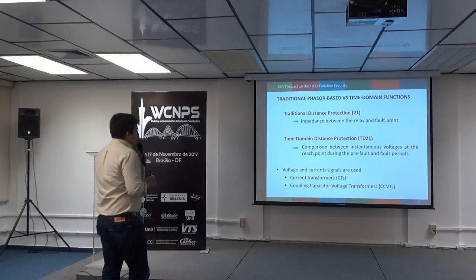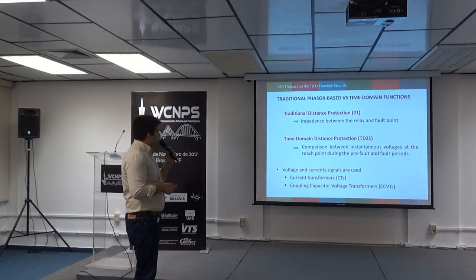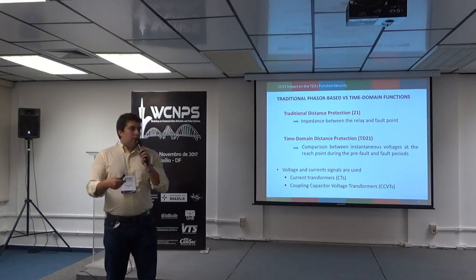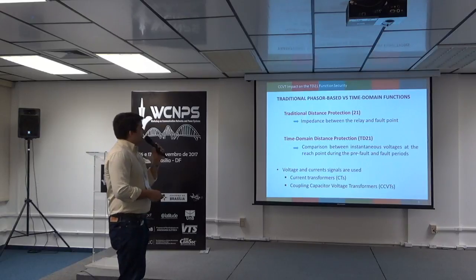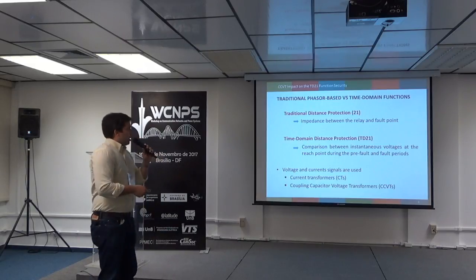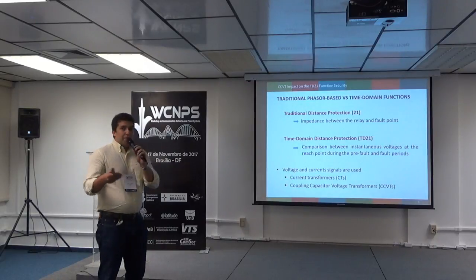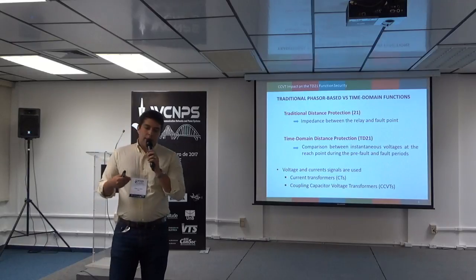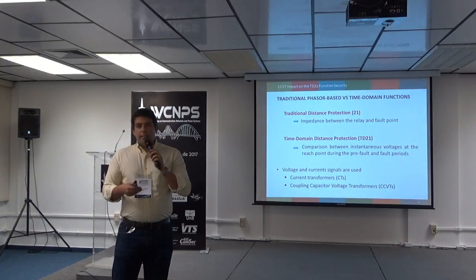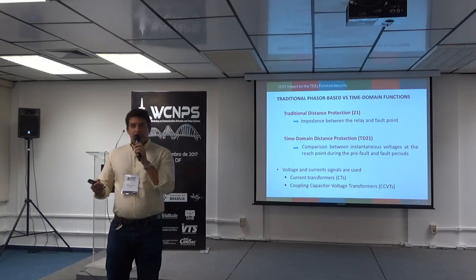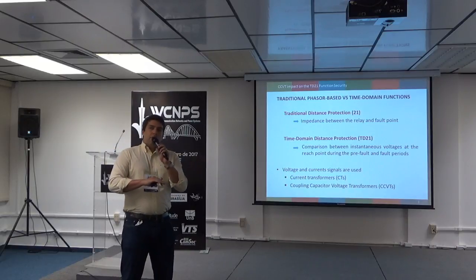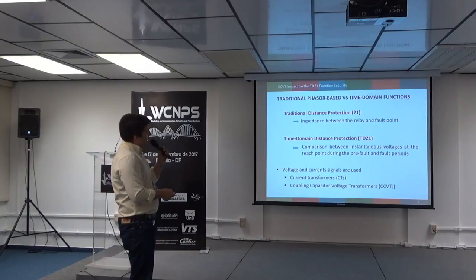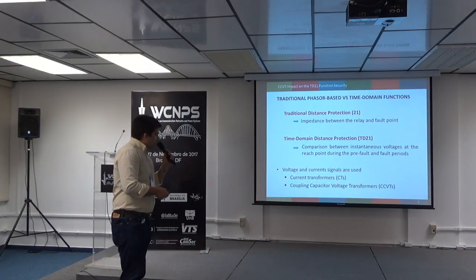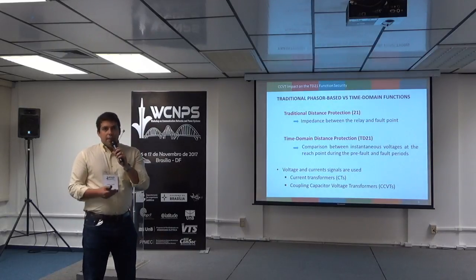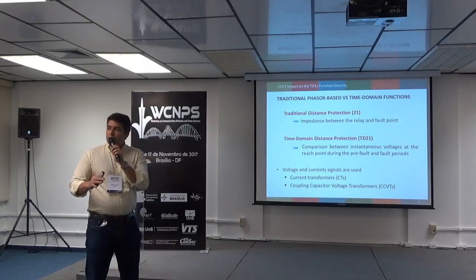In time domain distance protection, we have some little differences because we do not operate based on phasor information, but we use instantaneous values to operate. So we analyze the estimated voltage at the fault point, at the reaching point of this protection, computed using incremental quantities and the pre-fault quantities. The main goal of these incremental quantities is to analyze the pure fault circuit. So we compare the pure fault circuit voltage against the pre-fault circuit voltage. But in this case, we also have to use current transformers and coupling capacitor voltage transformers because we need voltage and current measurements taken from this equipment.